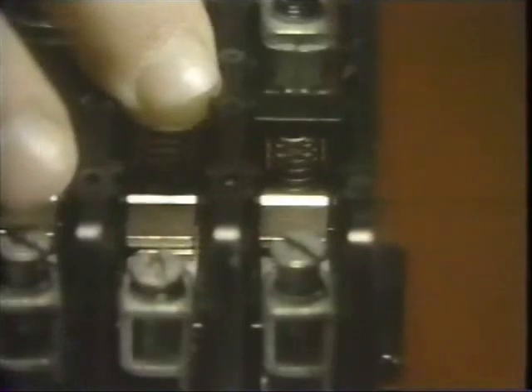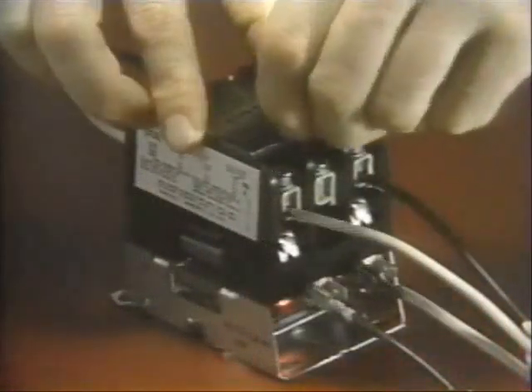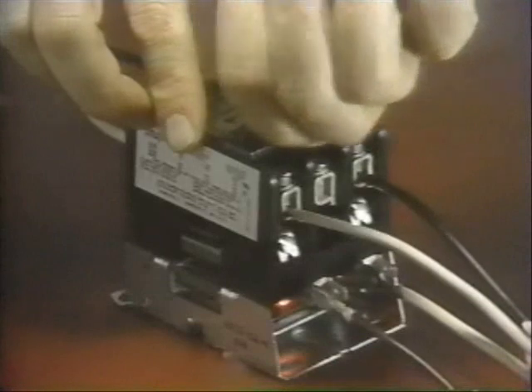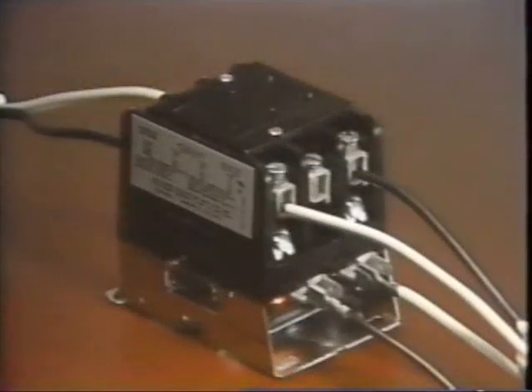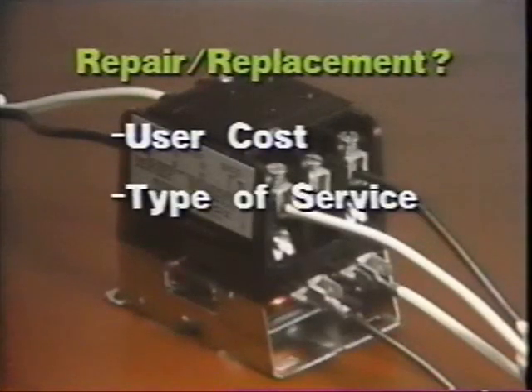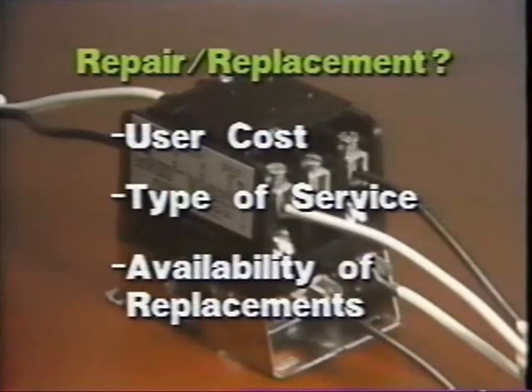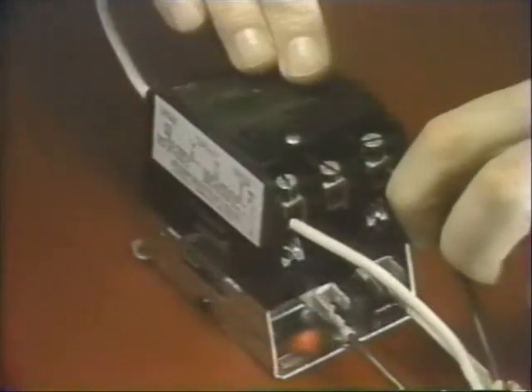After disconnecting the wiring and opening the top of the contactor, you are ready to take out the contacts. The terminal ends of the contact screw to the contactor frame. Springs hold the shorting bars in place. Complete the repair by thoroughly checking out the contactor. Whether you decide to replace or repair depends upon a number of factors: total cost to the user, type of service, and availability of replacements. You can also replace burned-out coils.